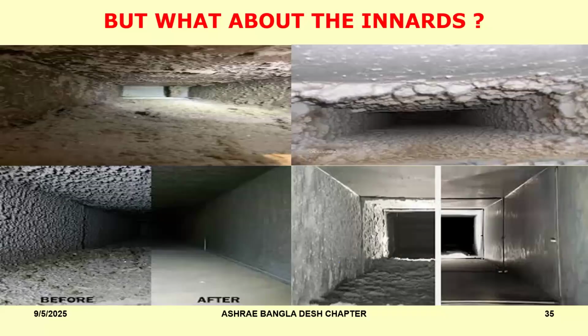Okay, you saw the outside of a duct. What about the inside of the duct? You'll be amazed. These are some pictures that I've got from ducts after they have been in operation for about 5 to 6 years. Sometimes you can get this state even after 2 to 3 years, depending upon the kind of dust loading, the levels of filtration, or the state of maintenance. So what it tells us is that if that's the state of the duct inside, no matter what we talk about IAQ, it's not really going to help, because this is going to make all of us feel very sick very soon. Of course, nowadays you have access to duct cleaning. In this picture here, you can see what the duct looked like before we cleaned it, and this is what it looks like after we cleaned it. So obviously this is what we want: this is what it was before, and this is what it is after.